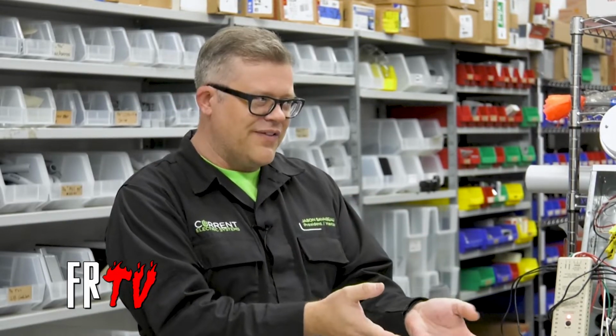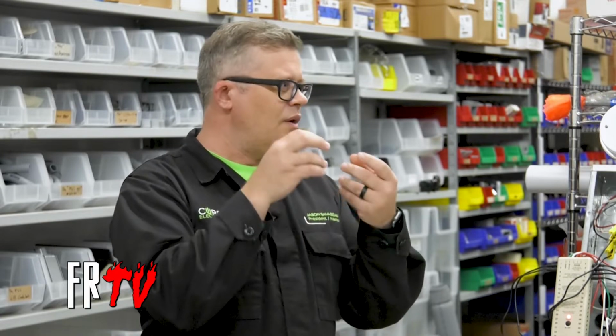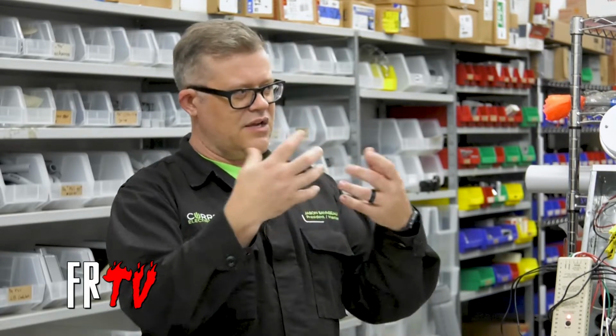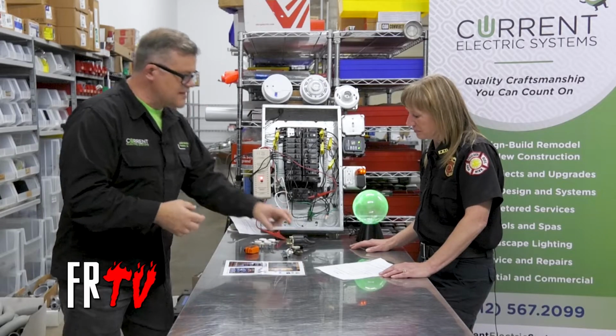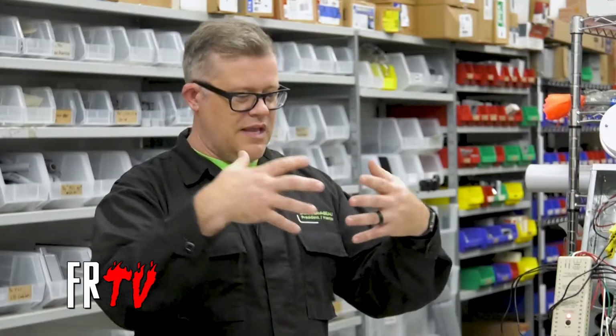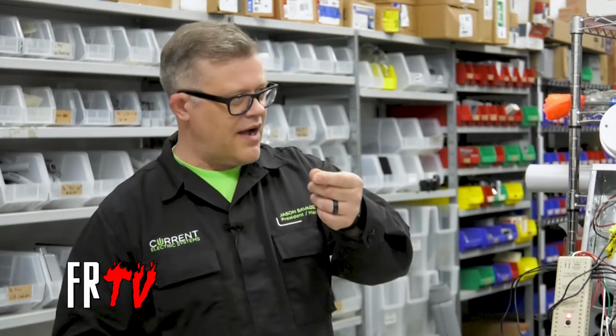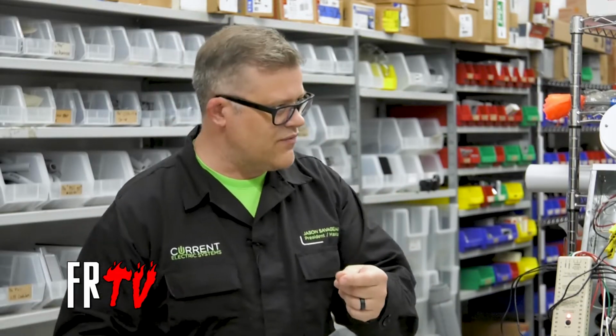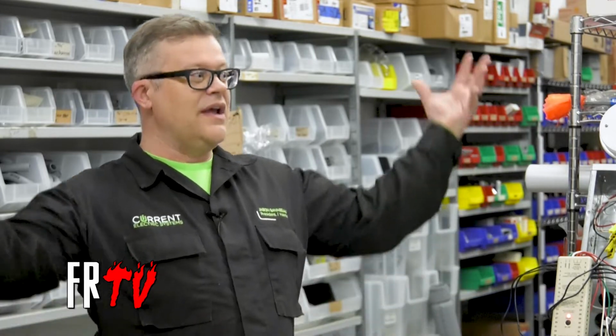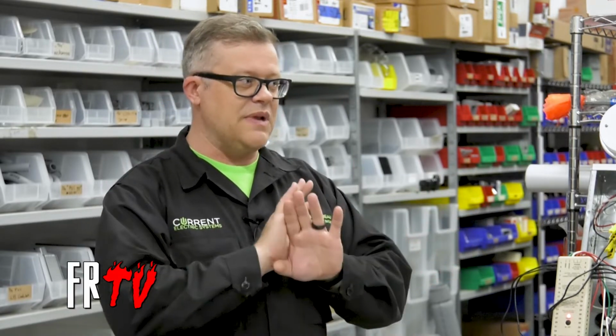And we've learned that that's not a great thing. So when a splice fails, it can cause burning and heat and fire. So in knob and tube, they would just splice, take off, and head wherever that was convenient. So you have these splices in the walls, you don't know where they are. And then when blowing insulation happened, they would encapsulate all that in insulation. And so now you have dust, insulation, fire potential. At the end of the day, knob and tube needs to be replaced. It's just not safe anymore.